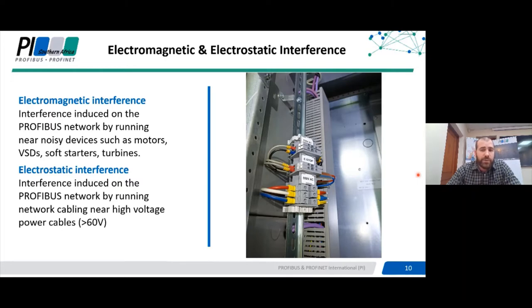If you connect a high speed oscilloscope on the bus, you will notice intermittent deformation of the waveform and even an occasional overlaid sinusoid. If connected to mains power, this is probably going to be at about 50 Hz. The second type is electromagnetic interference.